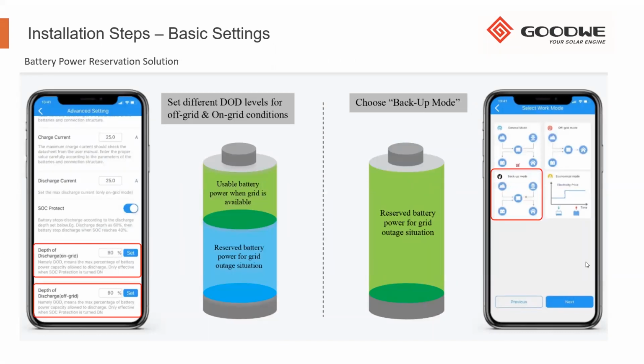I'm not going to go too much into this. I think Warren did cover this reasonably. I just want to highlight something which is sometimes a misunderstanding. We've got the depth of discharge on grid and the depth of discharge off grid. We somewhat need to see these as separate depths of discharge. Setting this doesn't reserve a certain amount. This just says to what state of charge we take our batteries.